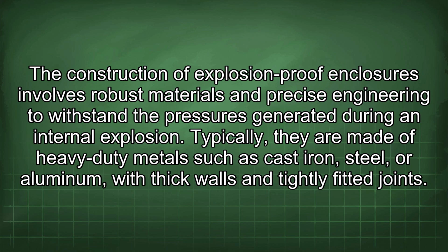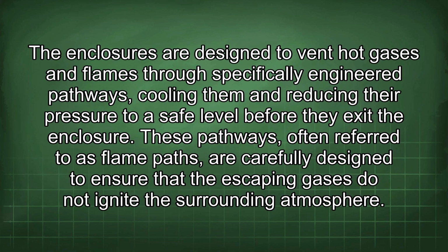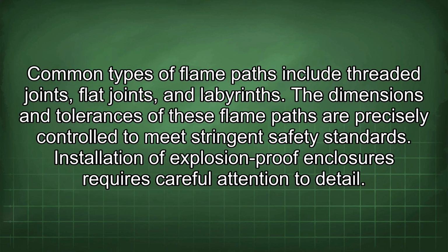and tightly fitted joints. The enclosures are designed to vent hot gases and flames through specifically engineered pathways, cooling them and reducing their pressure to a safe level before they exit the enclosure. These pathways, often referred to as flame paths, are carefully designed to ensure that the escaping gases do not ignite the surrounding atmosphere. Common types of flame paths include threaded joints, flat joints, and labyrinths. The dimensions and tolerances of these flame paths are precisely controlled to meet stringent safety standards.